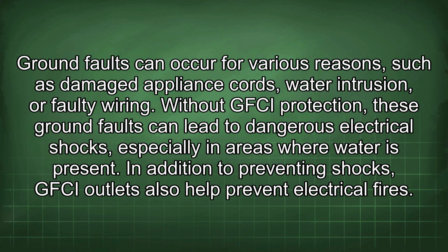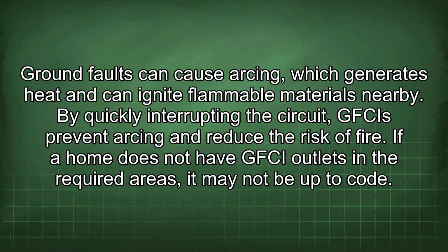Ground faults can occur for various reasons, such as damaged appliance cords, water intrusion, or faulty wiring. Without GFCI protection, these ground faults can lead to dangerous electrical shocks, especially in areas where water is present. In addition to preventing shocks, GFCI outlets also help prevent electrical fires. Ground faults can cause arcing, which generates heat and can ignite flammable materials nearby. By quickly interrupting the circuit, GFCIs prevent arcing and reduce the risk of fire.